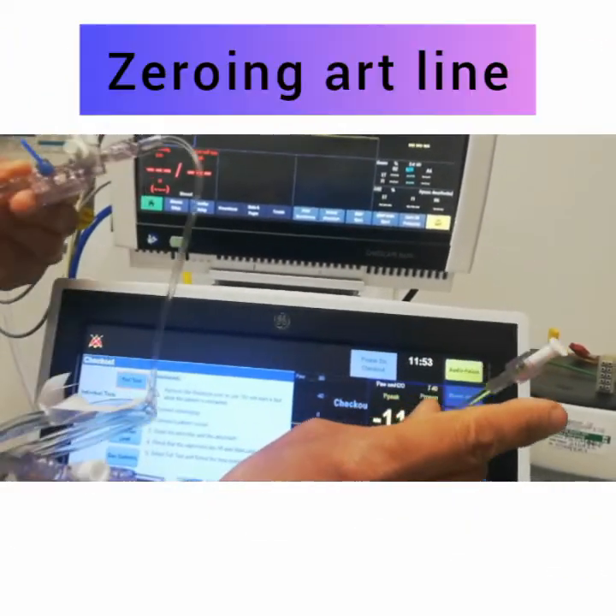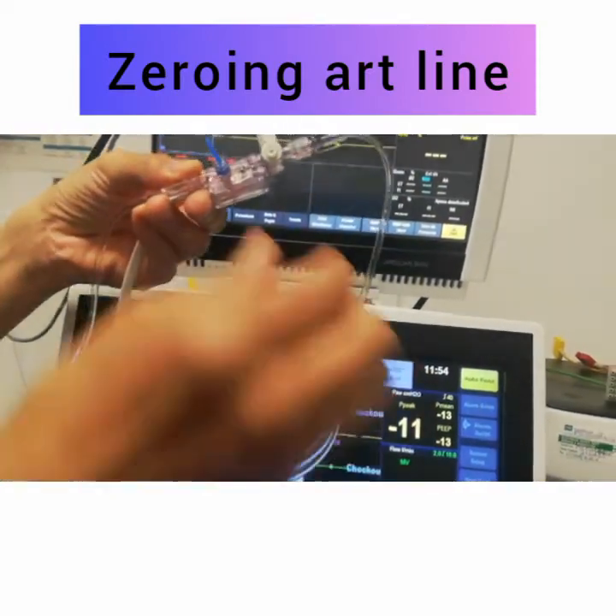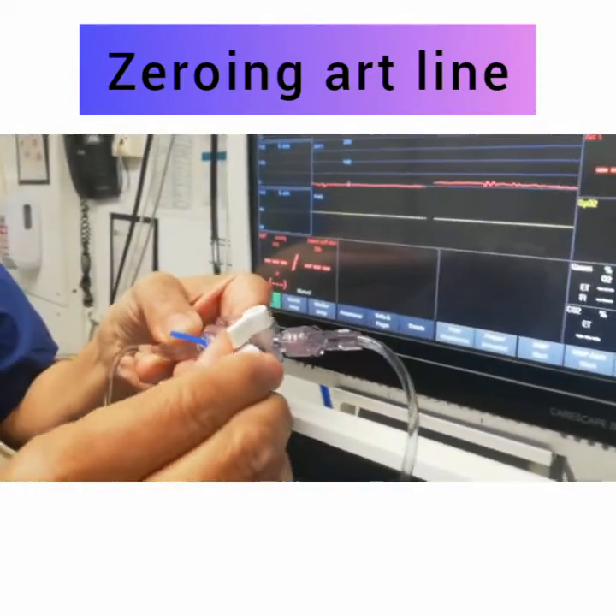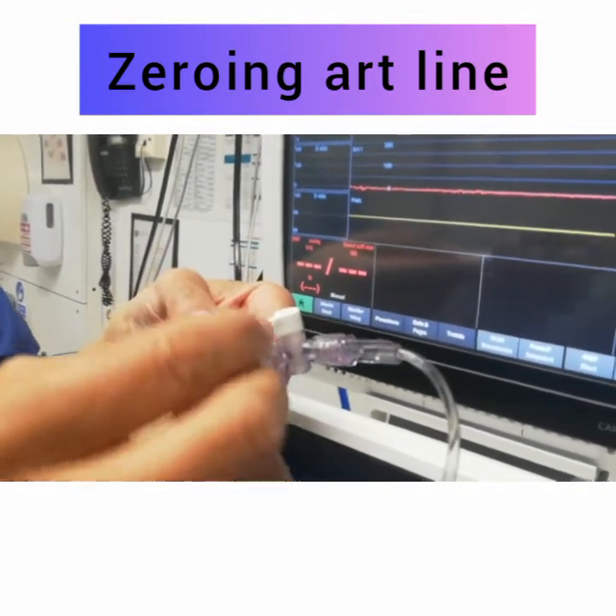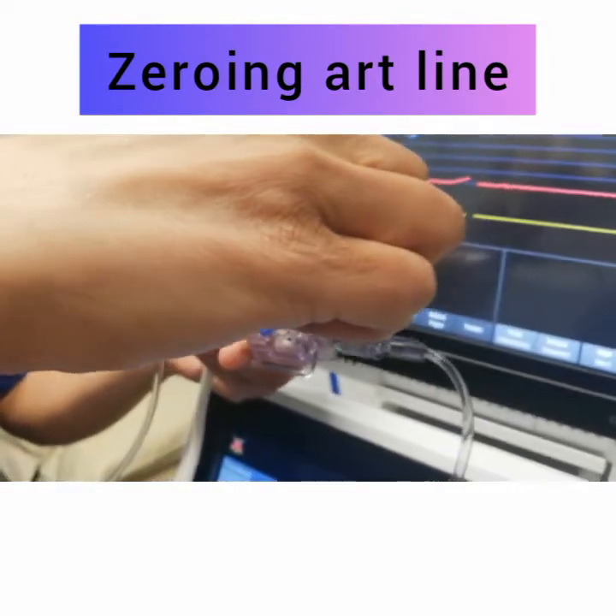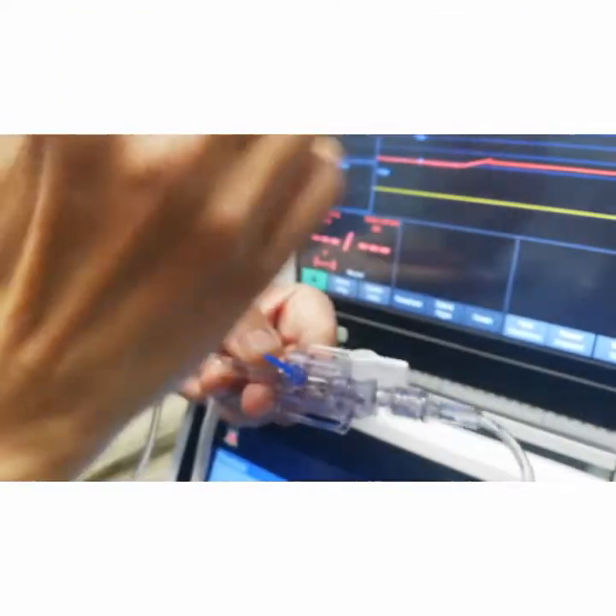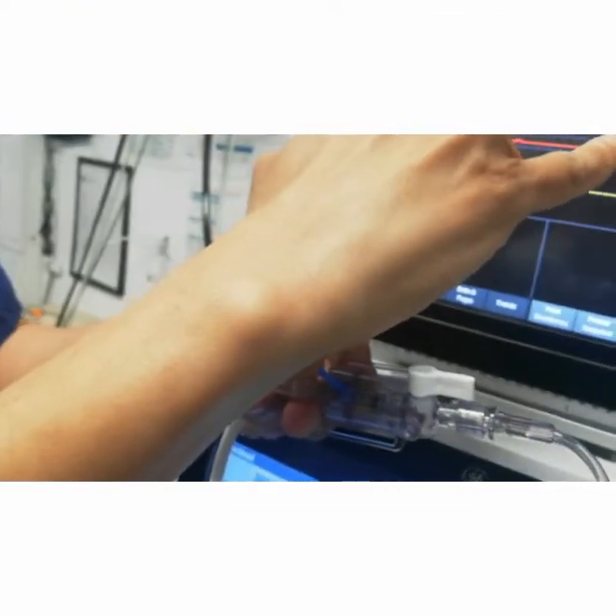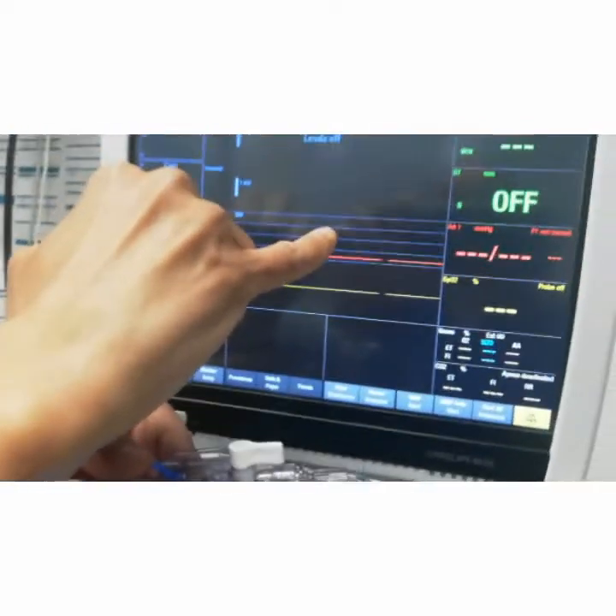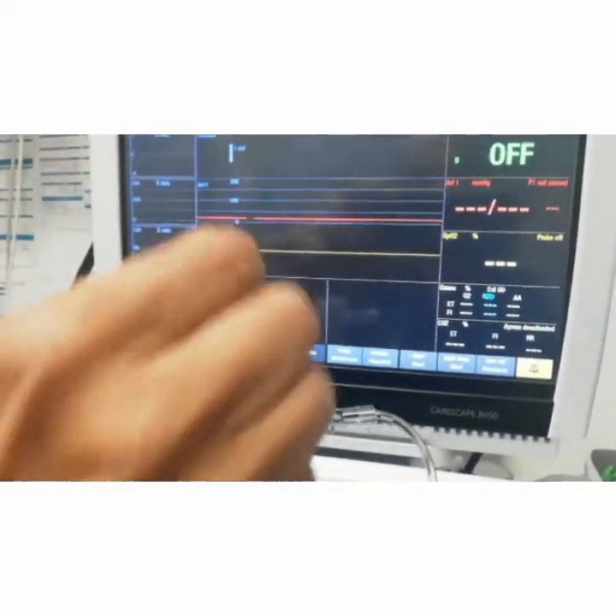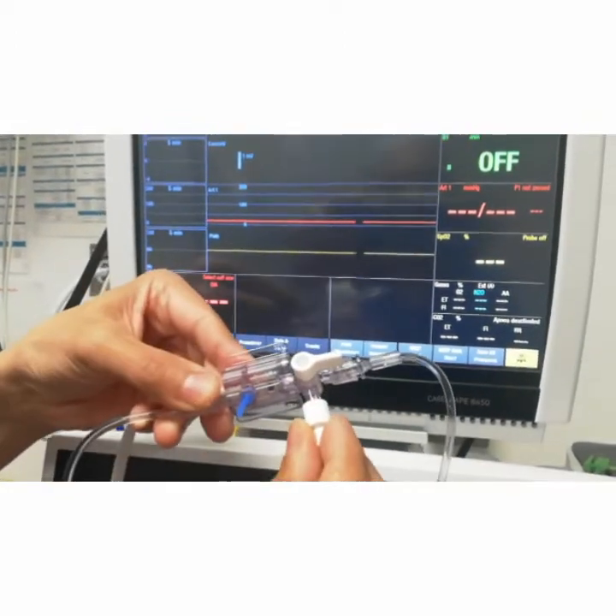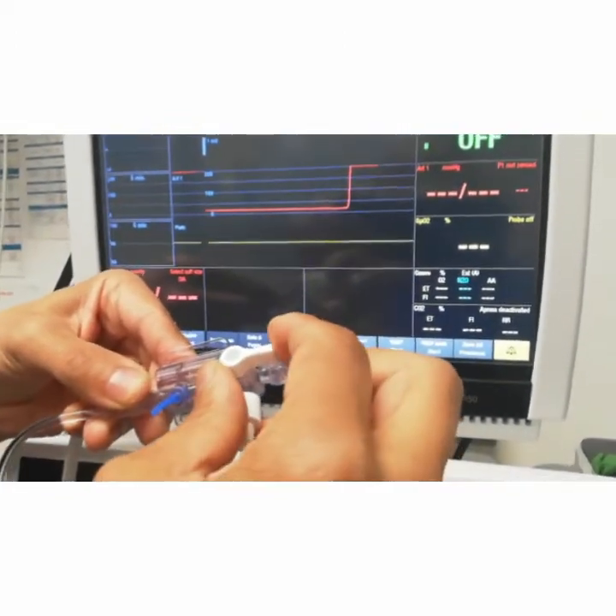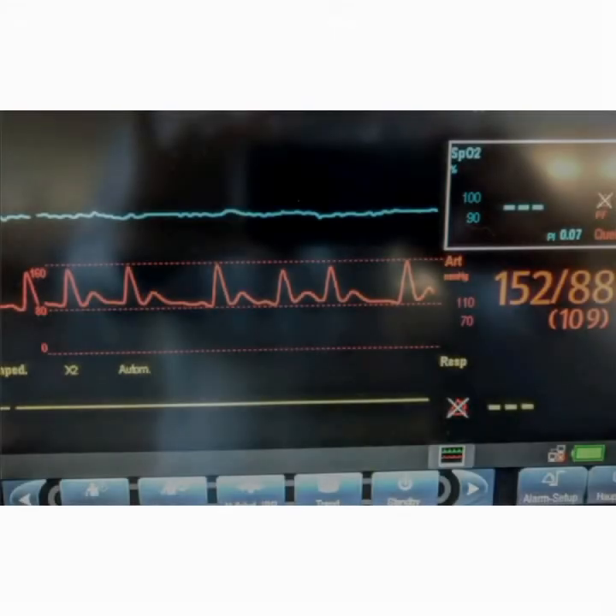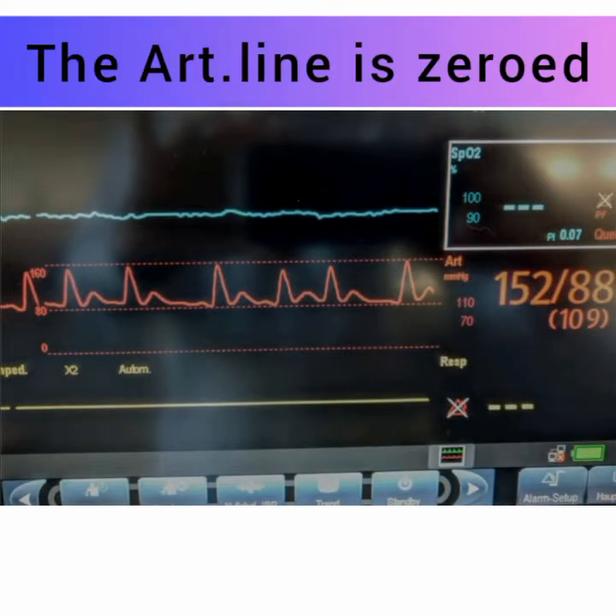Then to zero the line, simply take the cap off to atmospheric pressure, then turn the stopcock towards the patient and wait and look at the monitor. There is a red line. Once it's zeroed, put the cap back on and turn the stopcock towards the cap, and that's where you can see the line is zeroed. That's all you can see on the monitor.